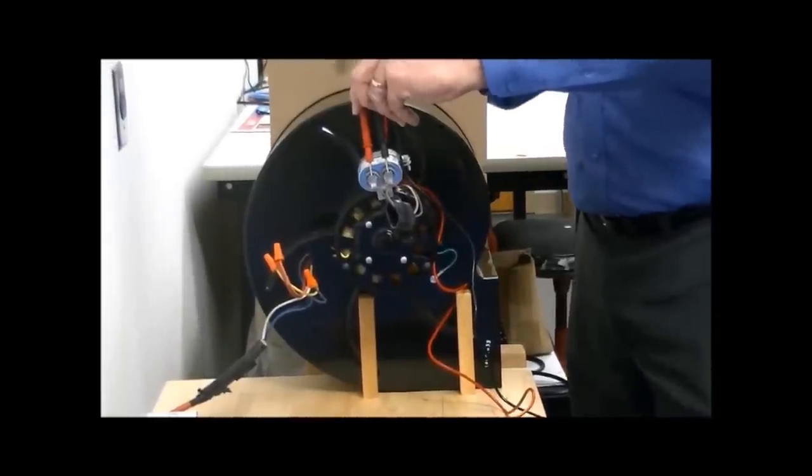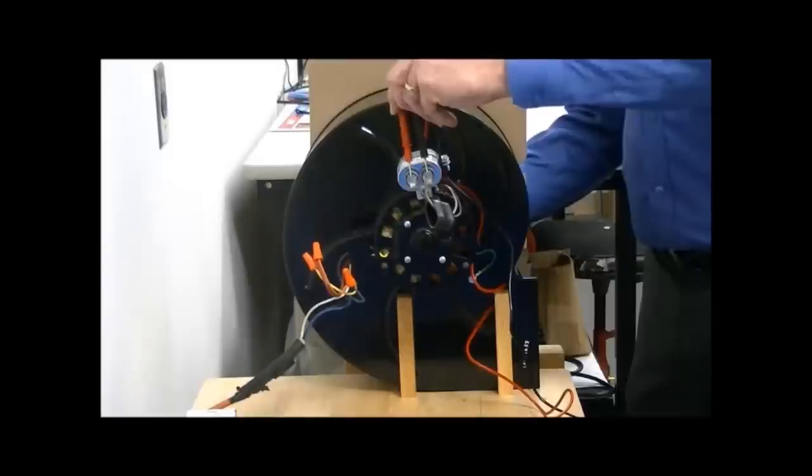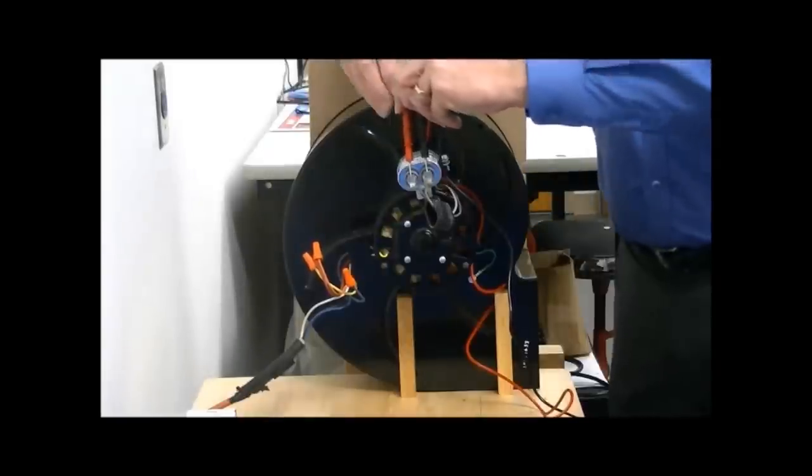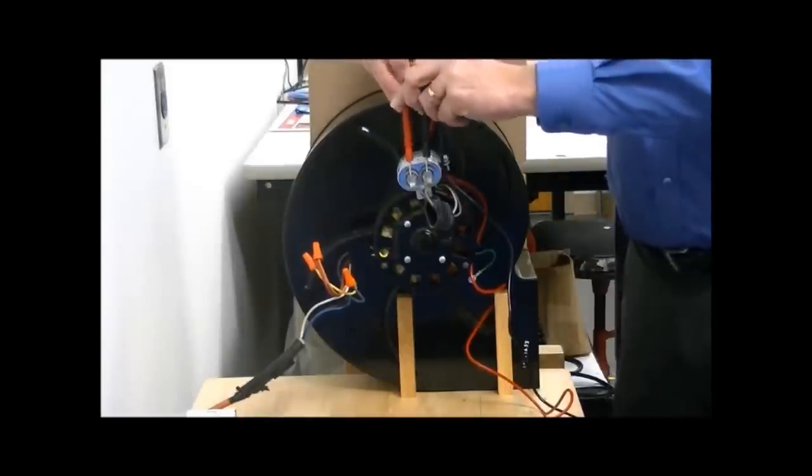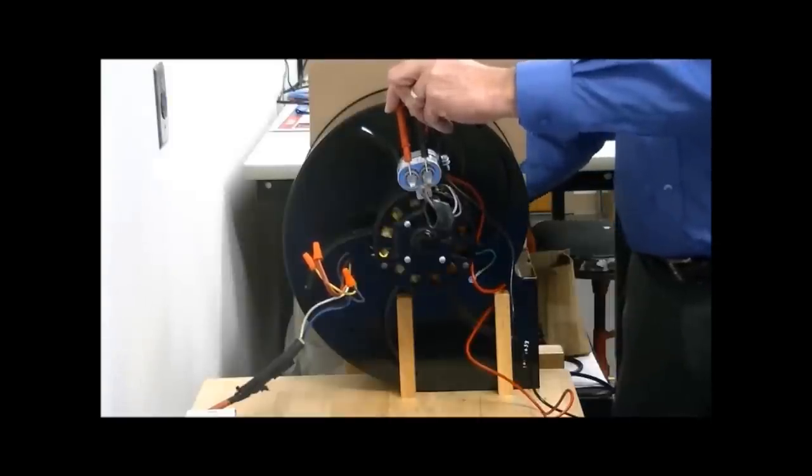As I completely restrict the air with dirty filters, my capacitor volts now exceed 400, which is a problem that will cause premature failure of a 370 volt capacitor.